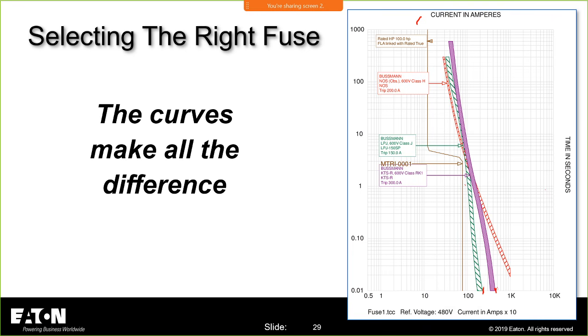They all fall in the window that's permitted by the National Electrical Code, but you'll notice that class J fuse is going to give me better protection on that motor from a short circuit perspective and still let that motor start in this instance. That's why I say whenever I'm looking at fuses, I'm really looking at these trip curves to figure out which one I want to use in my specific application.